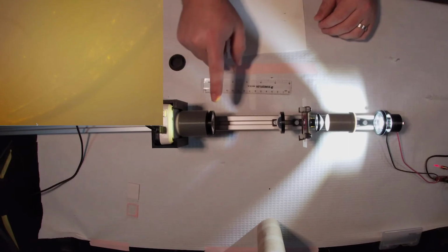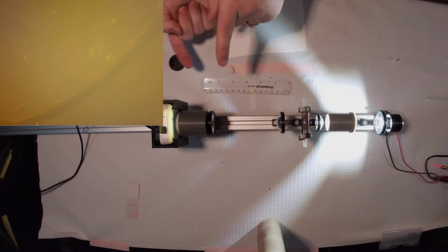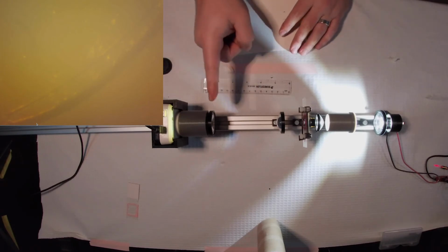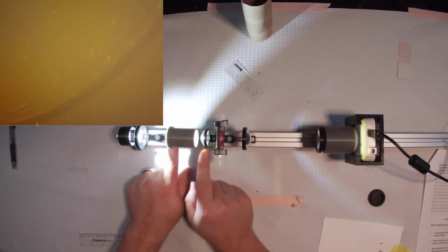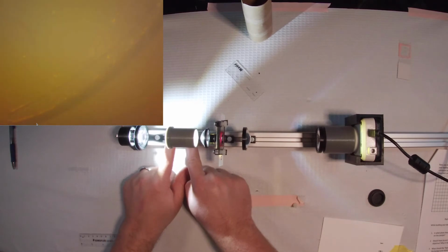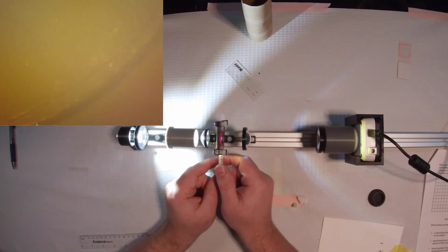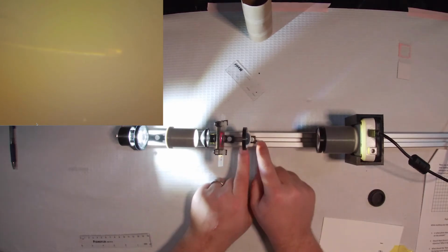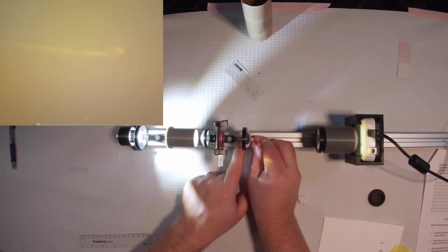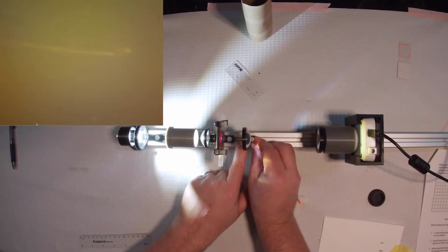tighten that down, and I will try to position it. Right, so you should have probably determined that the optimal place for our annulus is in the back focal plane of this condenser right here. So you can see it's very sensitive to any sort of changes in alignment. I'm just trying to adjust it so that my background is as dark as possible. Let's try to move to, yeah, I seem to have lost my hair in that installation, but there is my hair once more.